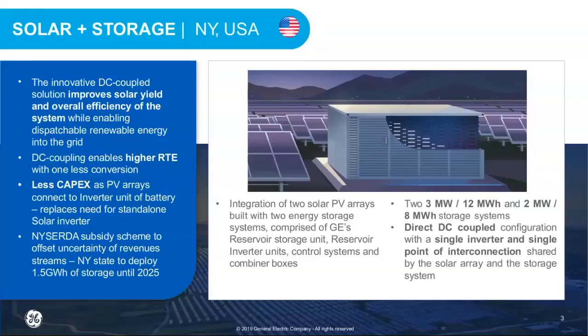Here's a particular project we did in upstate New York. It's a DC coupled system financed using debt and equity, with some NYSERDA funding provided as well. There are two solar arrays, with a one-to-one output — 5 megawatt solar coupled with 5 megawatts, 20 megawatt hours of storage underneath a single inverter. That means less CapEx, and they were able to take the entire ITC credit because of this.